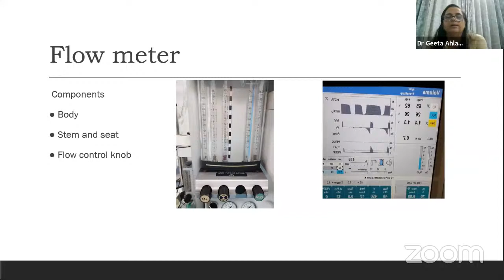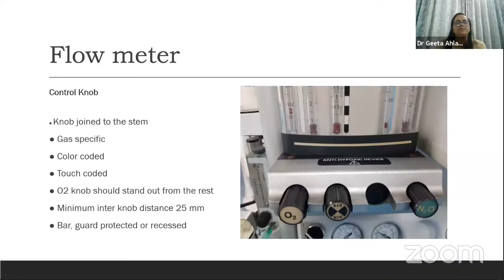They are touch coded. They are color coded. As I said, if there's no light or if you're busy ventilating a patient, your hand should know what knob you are operating and opening. So they are touch coded, their size is different, and they are at a minimum distance apart, at least 25 mm, so that you don't unnecessarily open or disturb the other one when you are trying to use another knob. In the newer machines, you can appreciate that there are digital flow meters with the most modern machines.